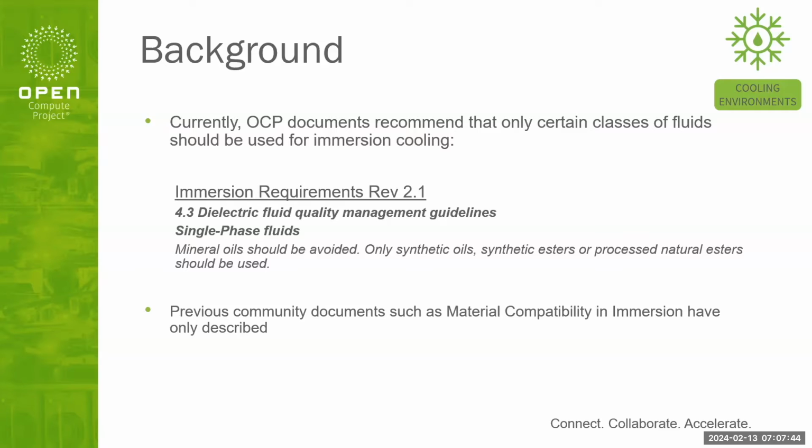In the single phase fluid section, there are statements that mineral oils should be avoided. Only synthetic oils, synthetic esters, or processed natural esters should be used. Sorry, I think this is an older version. The second point there should be that previous community documents, such as the material compatibility and immersion document, have only described certain types of base oils, which have not included what could be described as mineral oils.